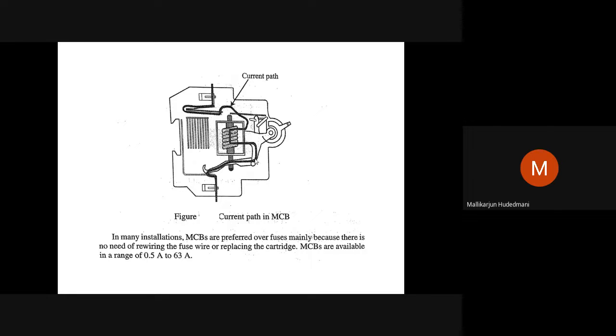To avoid that replacement, I have an MCB, miniature circuit breaker, connected in series between the power supply and the motor terminals. Suppose the motor has a fault. When you turn this switch on, automatically this knob falls down, trips down. Then you will understand this MCB has sensed the overcurrent absorption by the load. The load may be a motor, for example. Why is it absorbing? Definitely you will be cautious that there is a fault in the motor. Cables might have punctured and connected to one another, or there must be some short circuit in the mechanical assembly or electrical circuit, or a mechanical blockage in the rotor or pump might be the reason.